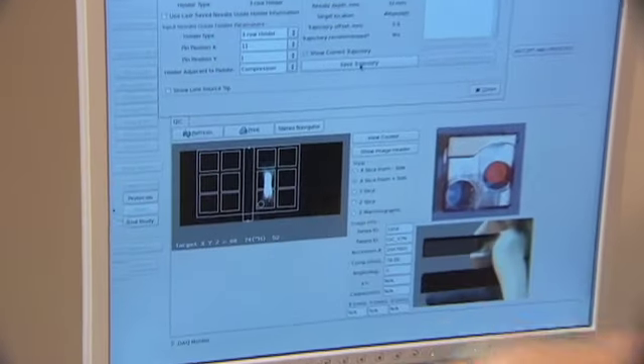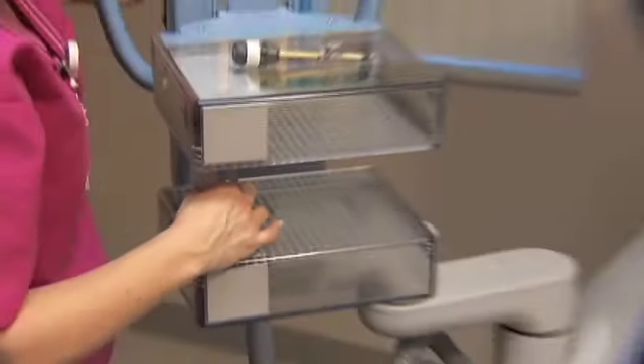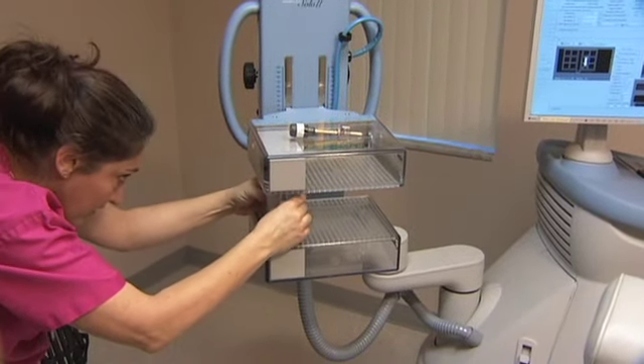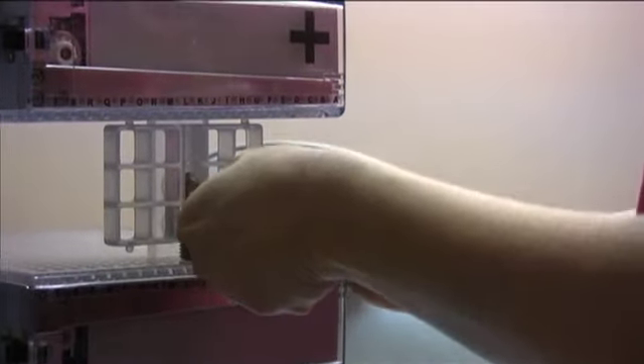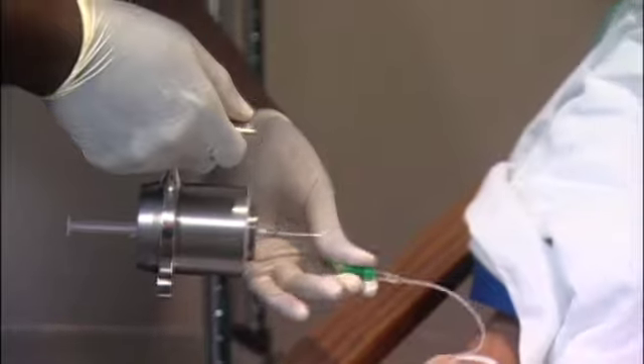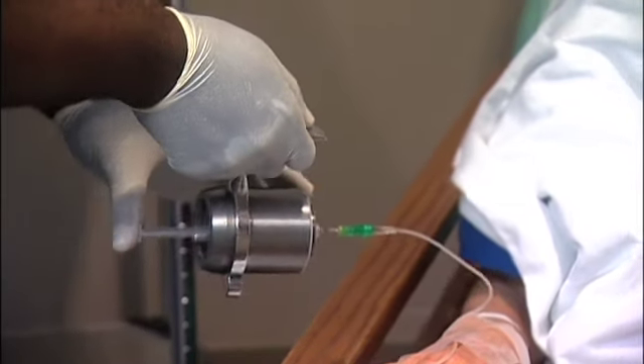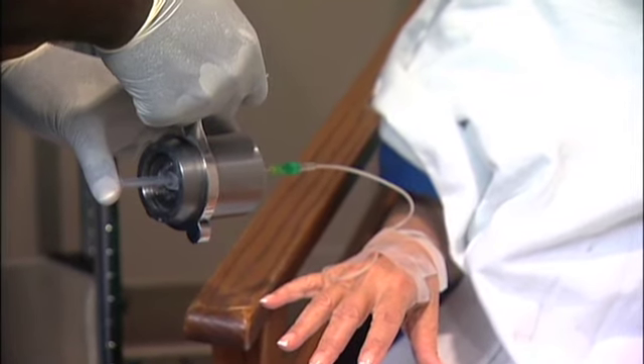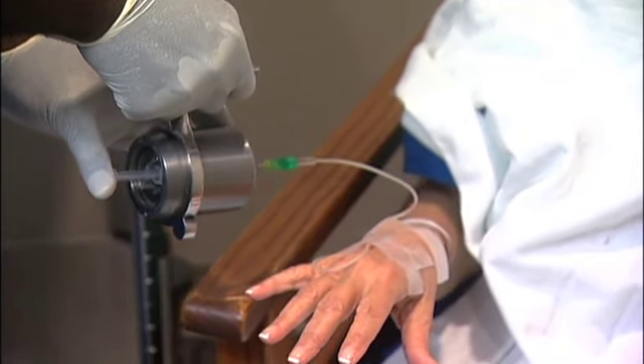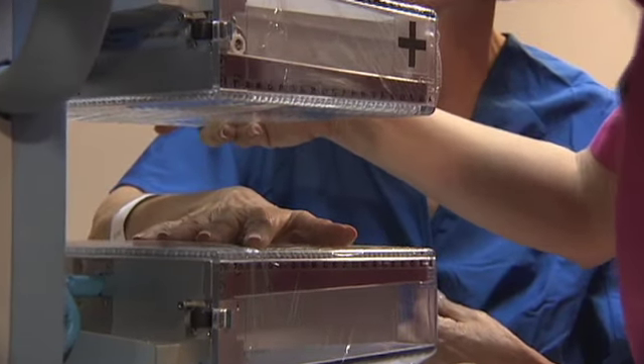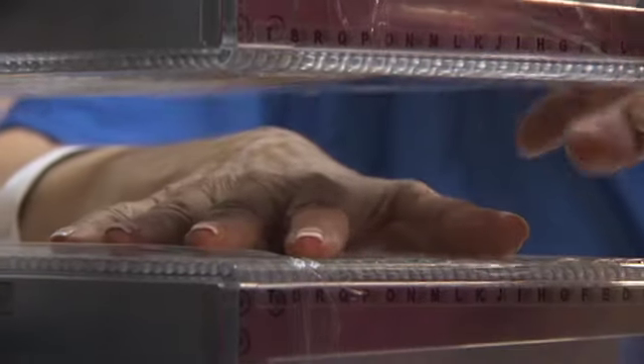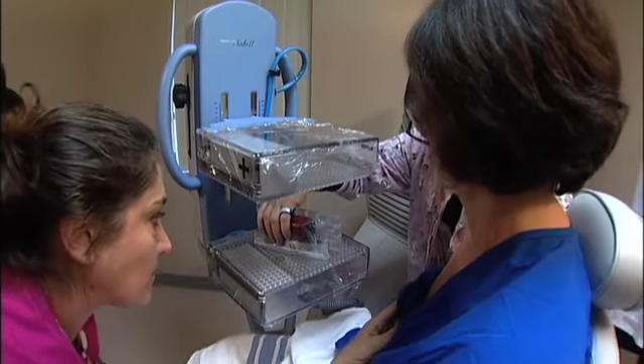Following the interventional planning session and before the patient is brought into the procedure room, the team then proceeds with setup and calibration of the PEM and Mammotome MI equipment. During setup, the clinical team may plan the placement of the needle guide holder, the support paddles, and the universal targeting set. Just prior to the equipment setup and calibration, the patient is injected with the radiotracer FDG18, a radioactive sugar. The patient is instructed to rest quietly for about 1 hour to allow the radiotracer to work its way through the body. A quick, low-resolution 4-minute PEM scan is performed, usually of the hand, to confirm adequate uptake of the radiotracer. The patient is then positioned, and the breast is immobilized.